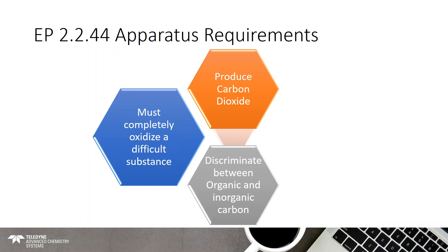The apparatus requirements stated by EP 2.2.44 for your TOC system are actually very vague. All it really says is: the instrument must be able to produce carbon dioxide; it can use any oxidation technique to convert organic carbon to CO2; and it must be able to discriminate between organic and inorganic carbon. However, it doesn't specify whether you must use TC minus IC or TOC — it says you can use either. As long as the instrument can meet the system suitability test, the technique is not important.